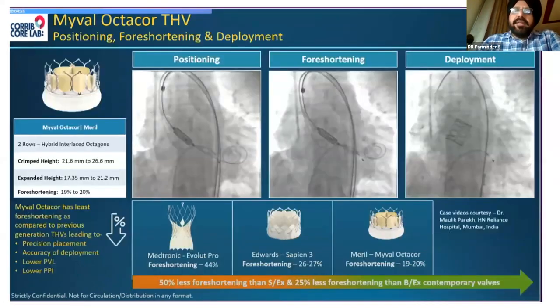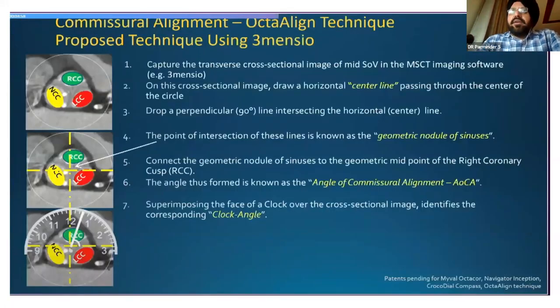And the foreshortening while deploying is quite low in Octacor in comparison to Edwards, as well as in comparison to Evolut Pro. It's only 19 to 20% versus 26% and 44% for Edwards and Medtronic Evolut Pro. This is because of the octagonal cell design in Octacor. So the positioning of this valve would be better during deployment. It won't change much, whereas the Edwards valve usually shrinks from the LV cavity side and moves a little bit up when you deploy it, when it expands. Further, commissural alignment is also in the pipeline for this valve, and it's possible with this valve using a technique for which they have pending patents.